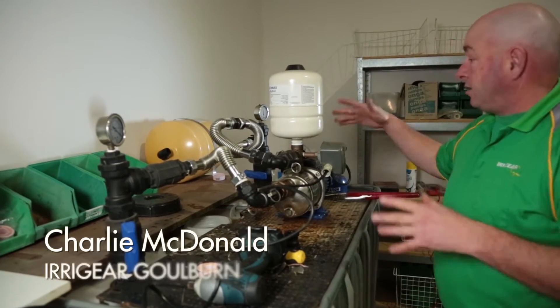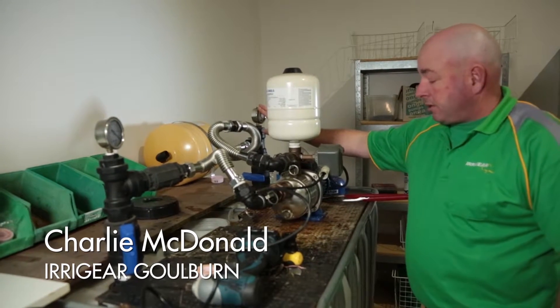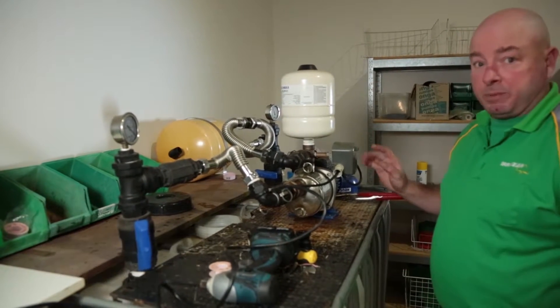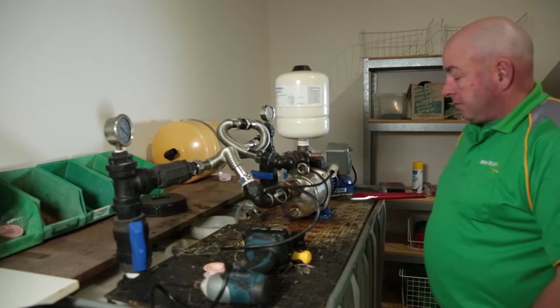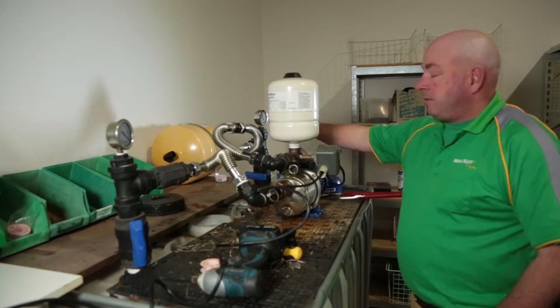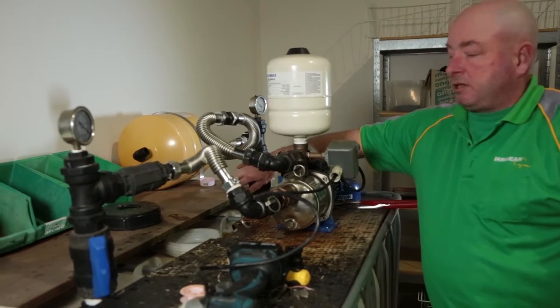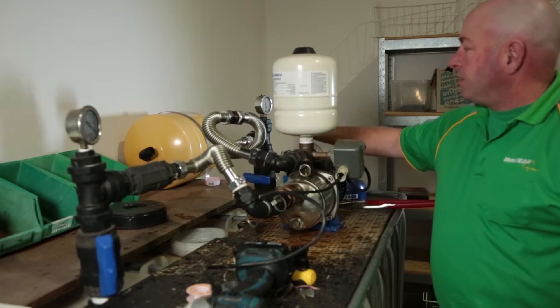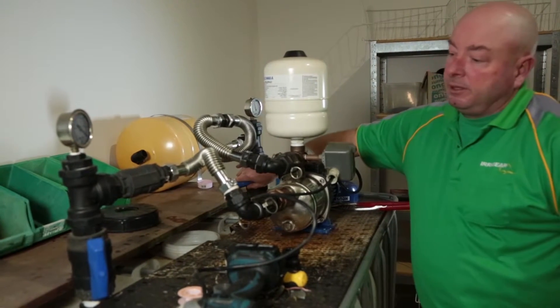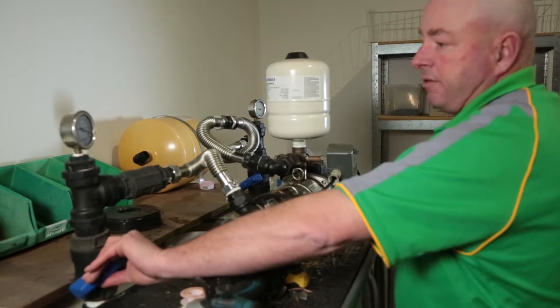We're testing that the pump's doing its proper pressure that it should be doing, because each pump has a level that it should work to. We're checking that it's turning off and turning on okay, that it's behaving the way it should.